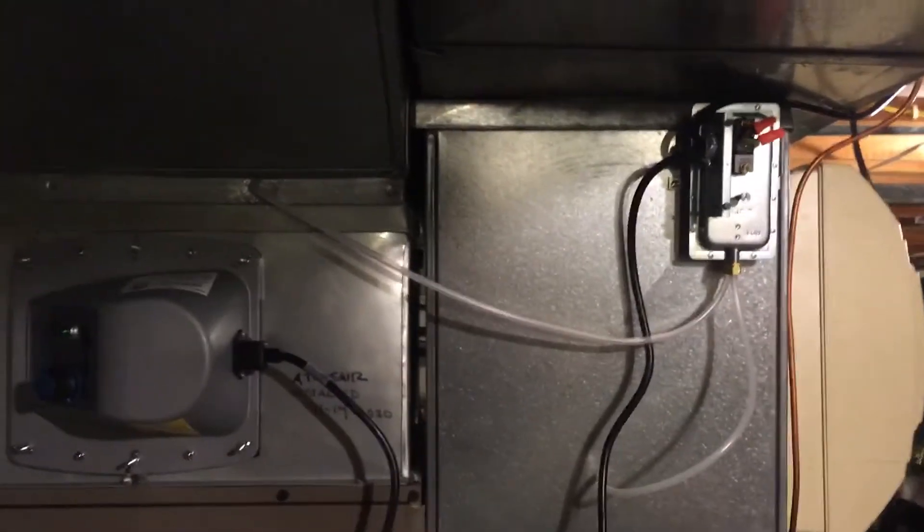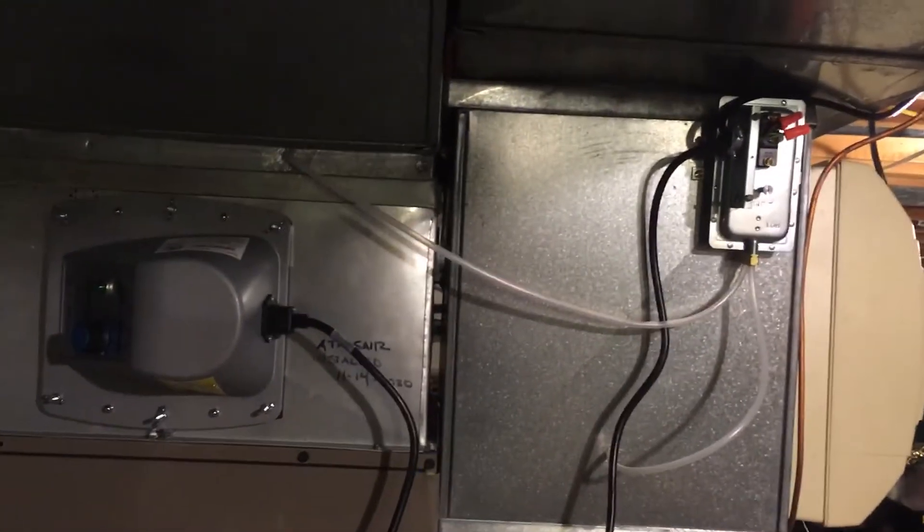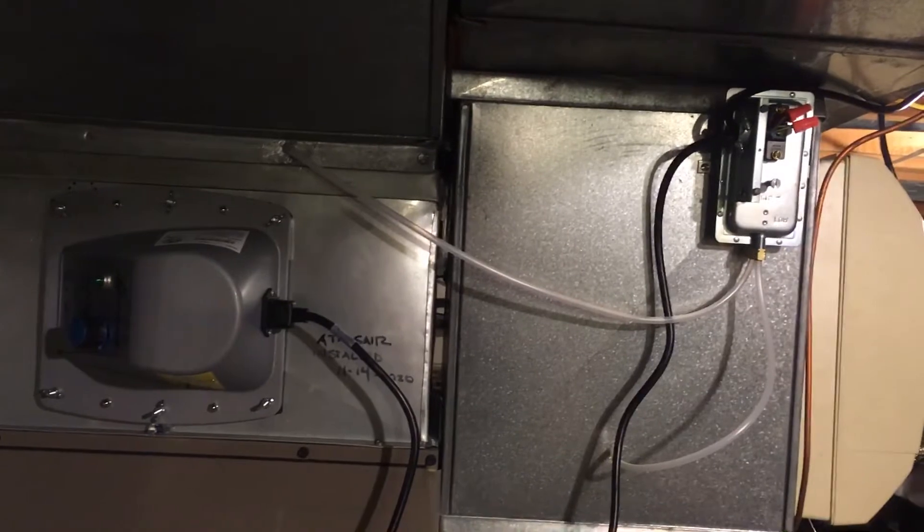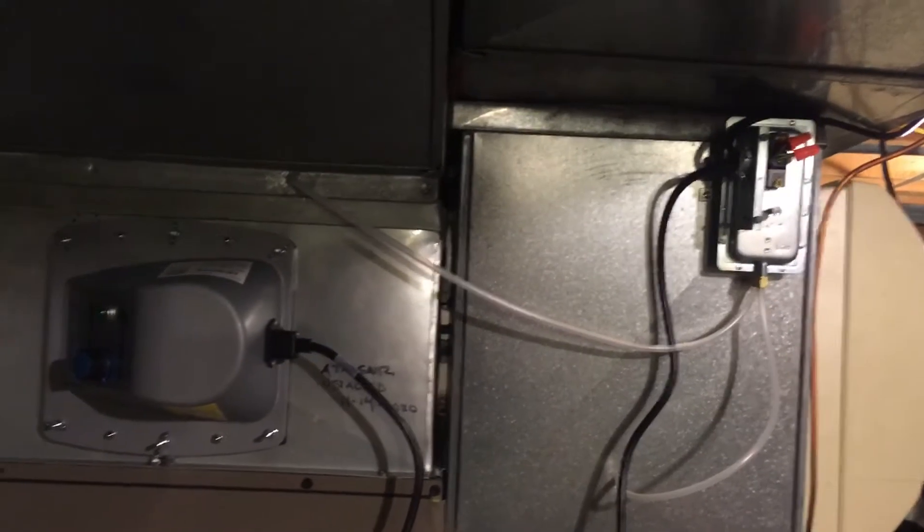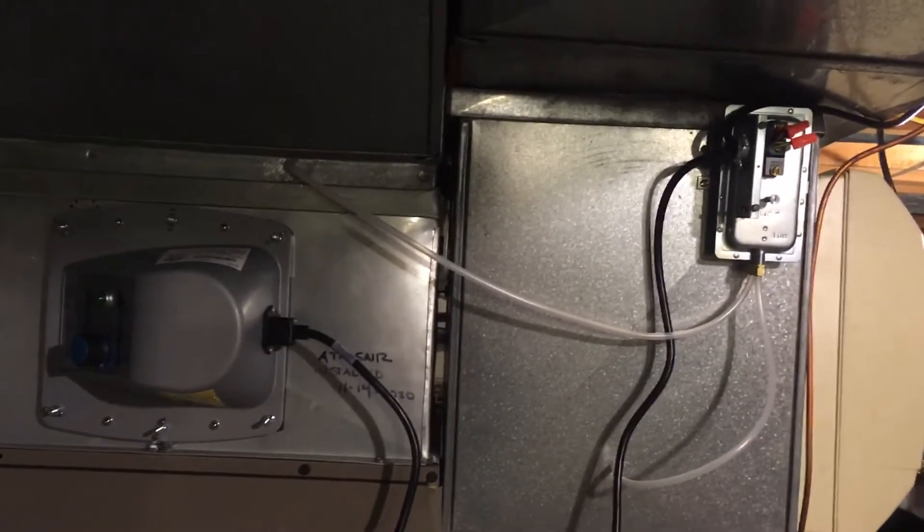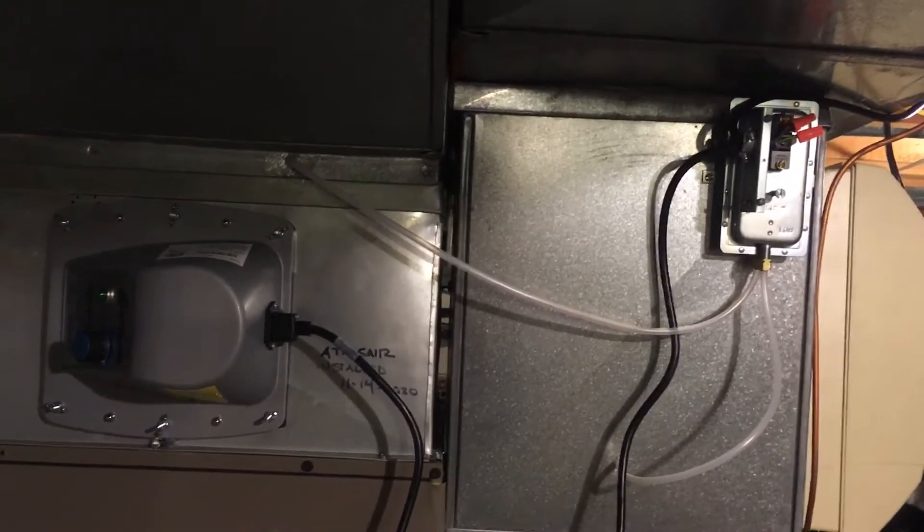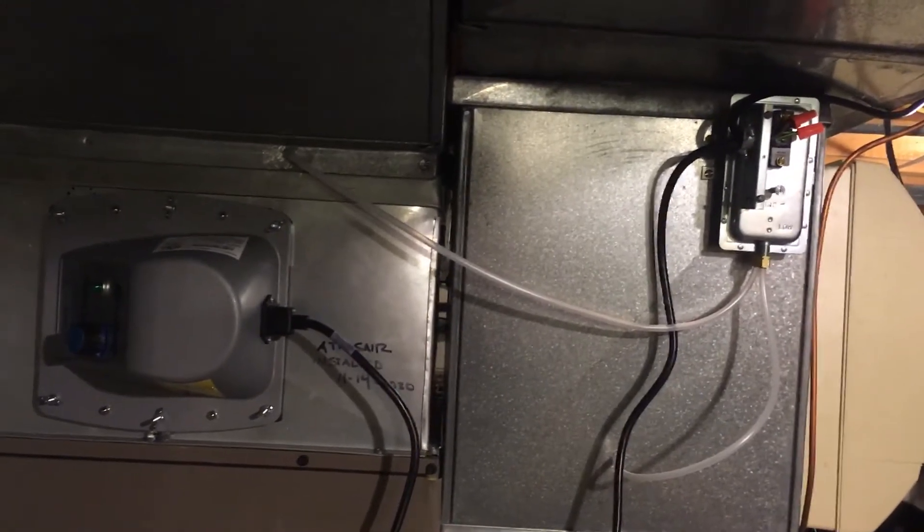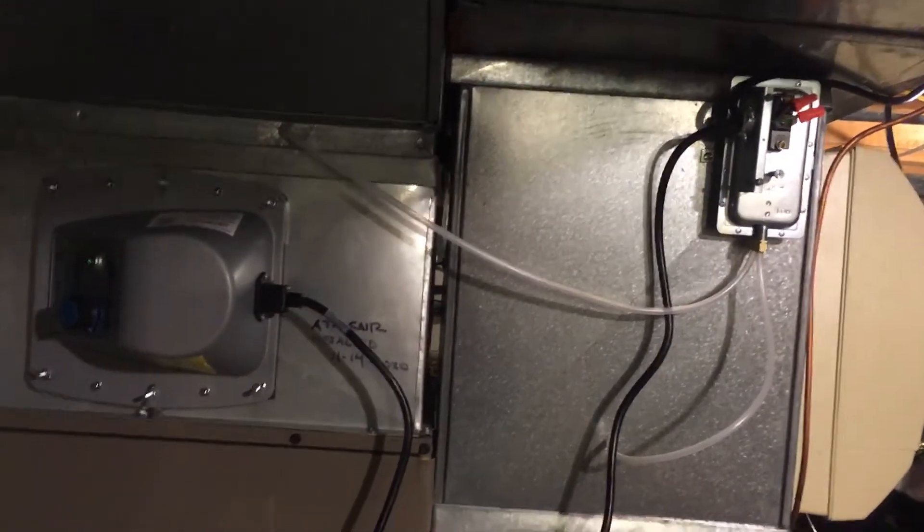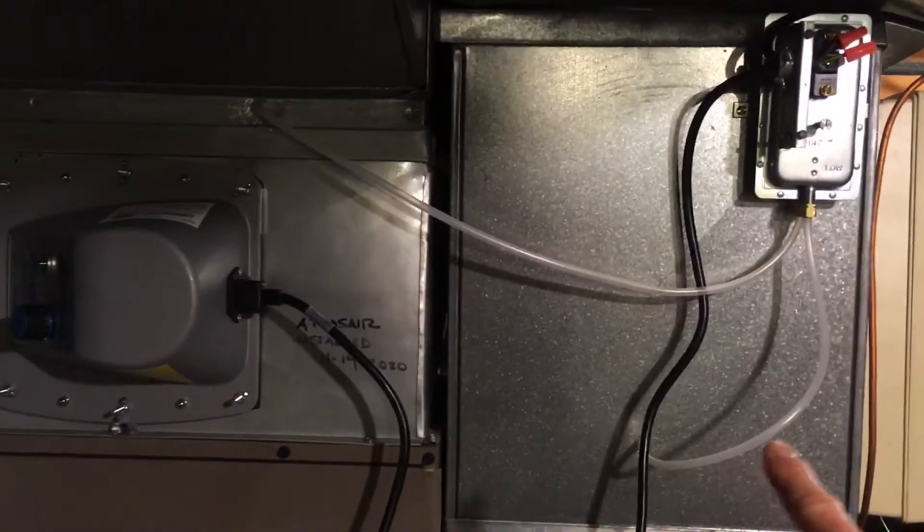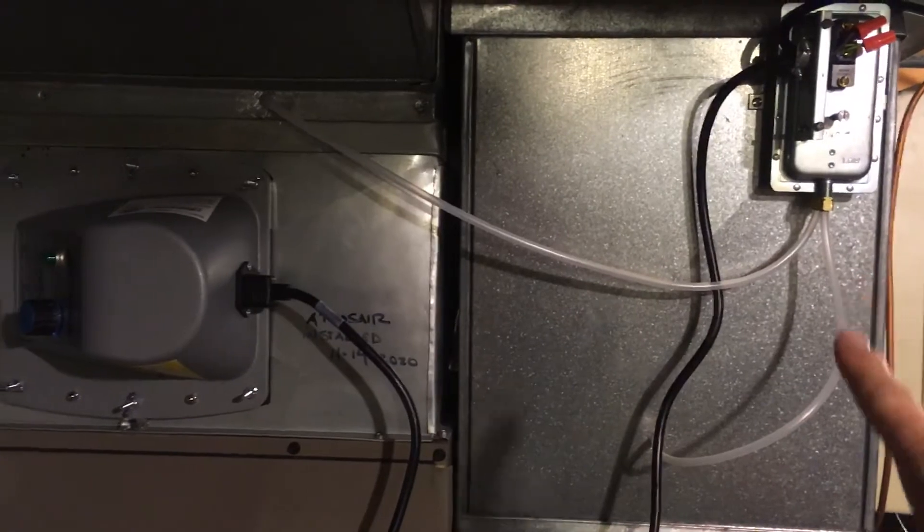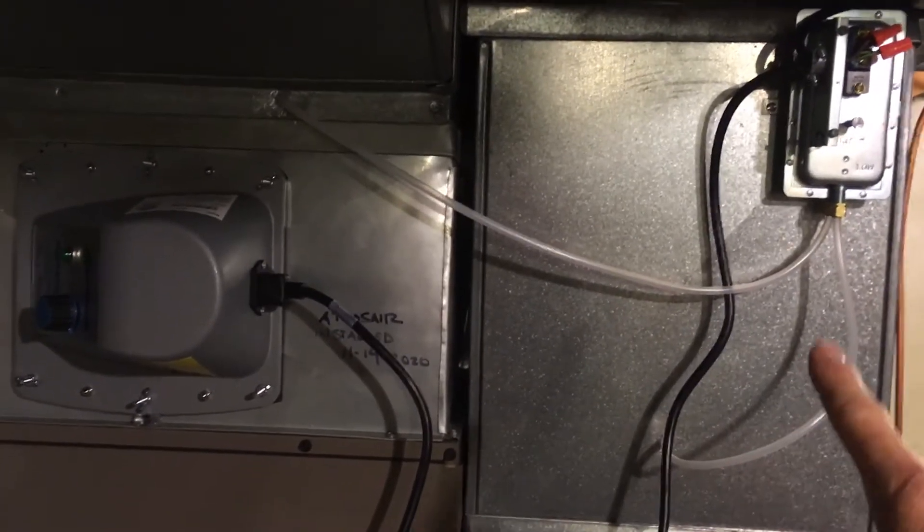Hey guys, another quick video on problems with this airflow switch. I have a modulating fan on my furnace and I was not able to get this switch to make until I added a negative pressure line to my return air duct right here.